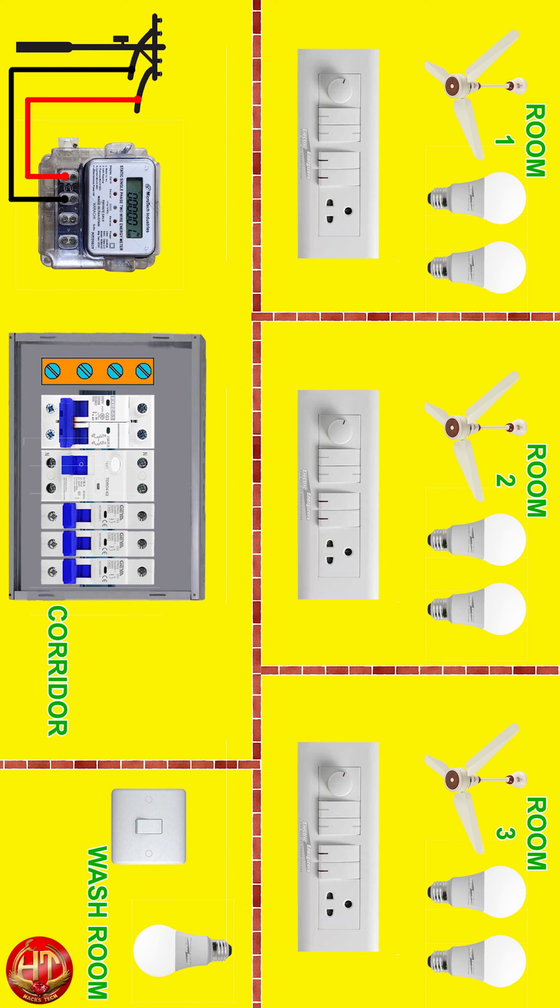Third terminal outgoing neutral wire with any one bottom terminal of the 2-pole MCB, and fourth terminal outgoing phase wire with the other bottom terminal of the 2-pole MCB.